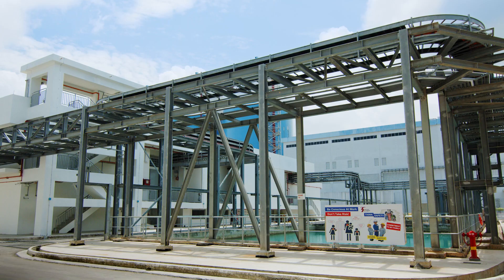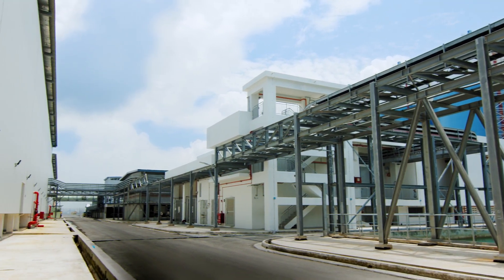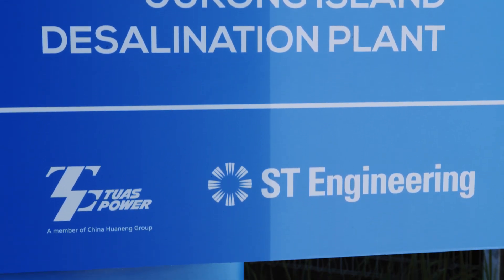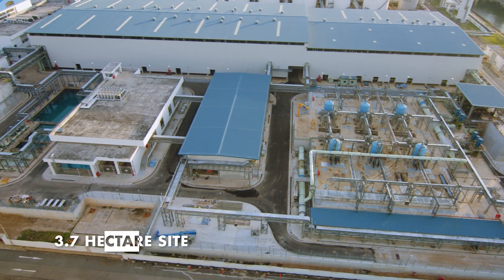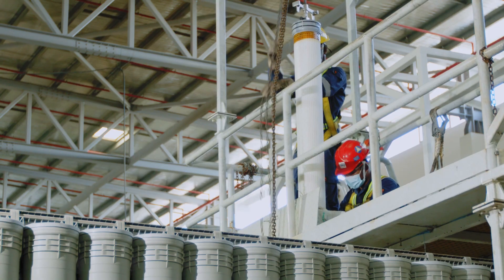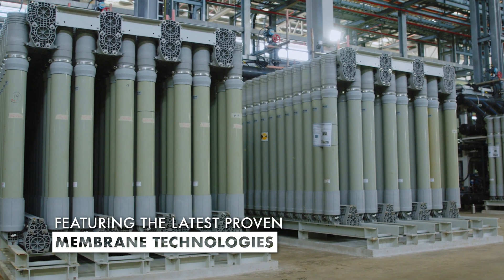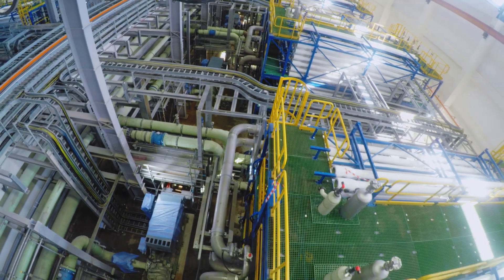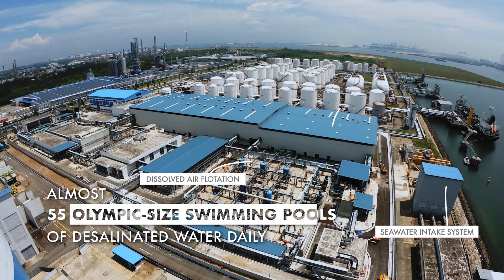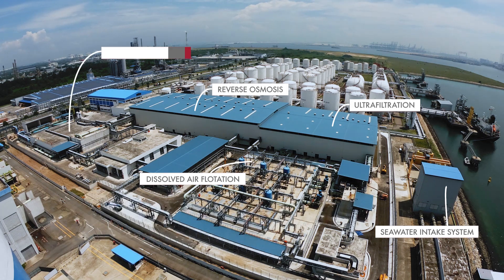The Jurong Island Desalination Plant, or JIDP, is the latest development in Singapore's water story. JIDP, jointly developed by Tuas Power and ST Engineering, sits on a 3.7 hectare site in Tembusu, Jurong Island. JIDP uses the latest proven membrane technologies in ultrafiltration and reverse osmosis, adding another 137,000 cubic meters — or almost 55 Olympic-sized swimming pools — of desalinated water a day to Singapore's water supply.